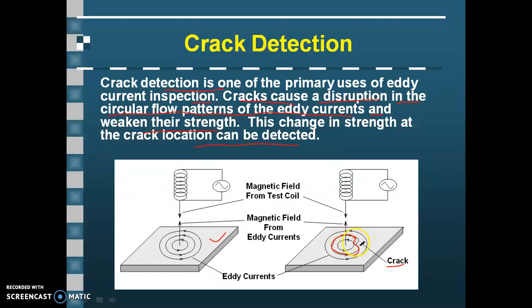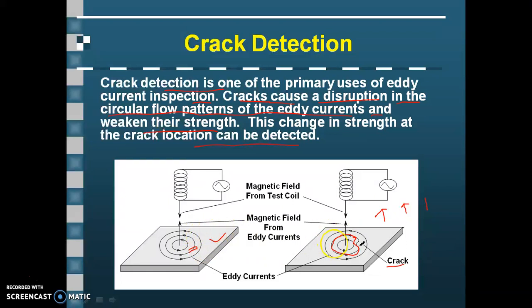Because of this distortion in shape, the strength of the electromagnetic field produced by the eddy current will decrease. As the strength of the electromagnetic field produced by the eddy current decreases, the overall electromagnetic field of the system will increase, so the current will increase, and the impedance will not increase as much compared to the crack-free case. For the crack-free case, impedance will increase by a much greater amount because the opposing electromagnetic field is very strong. But for the cracked case, as the opposing electromagnetic force is weaker, the impedance value will not change in the same fashion — it will increase by only a little amount.